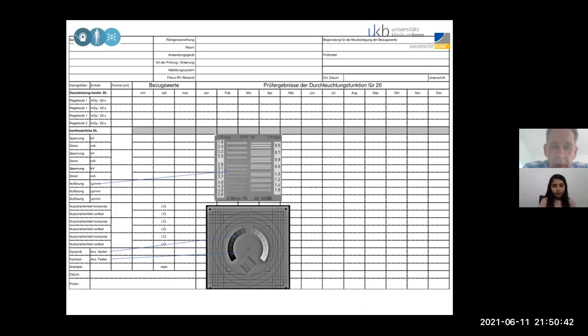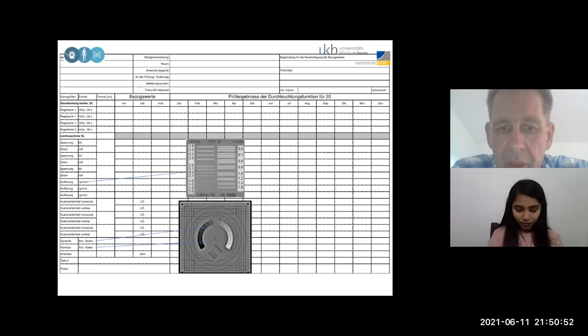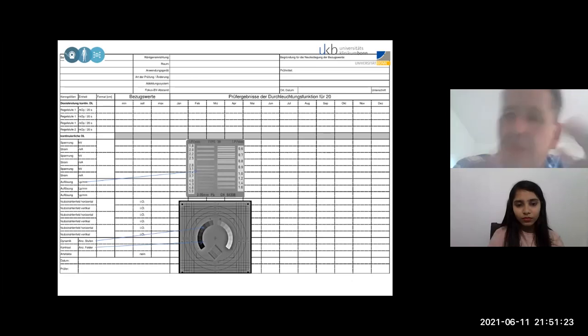The line pairs per millimeter, that is a typical phantom for line pairs per millimeter. That is something which should be used in the acceptance test, and is usually included in the full phantom in the lower corner. And then you see the dynamic steps from white to black. If you look carefully, unfortunately my imaging is not good for diagnostics. You should see circles in the inner circle, just near the steps, at least four circles. This is something you should check as a constancy check referred to the acceptance test.